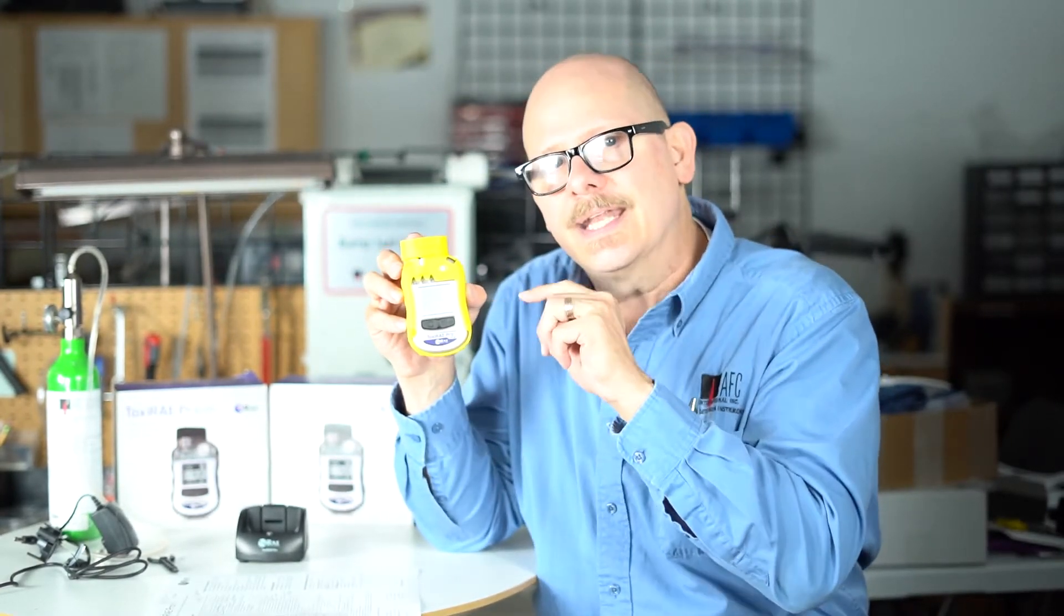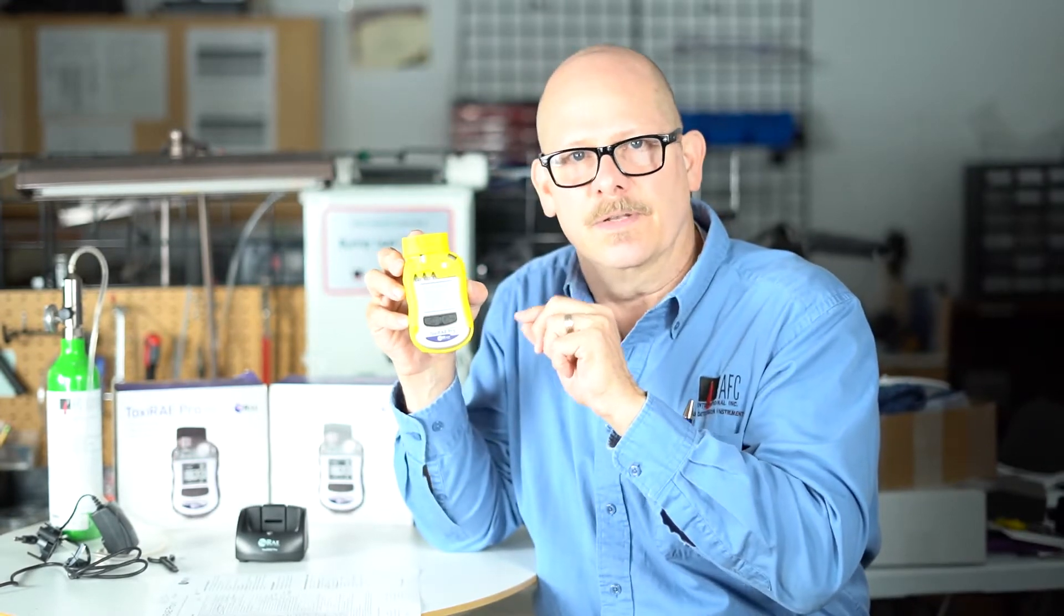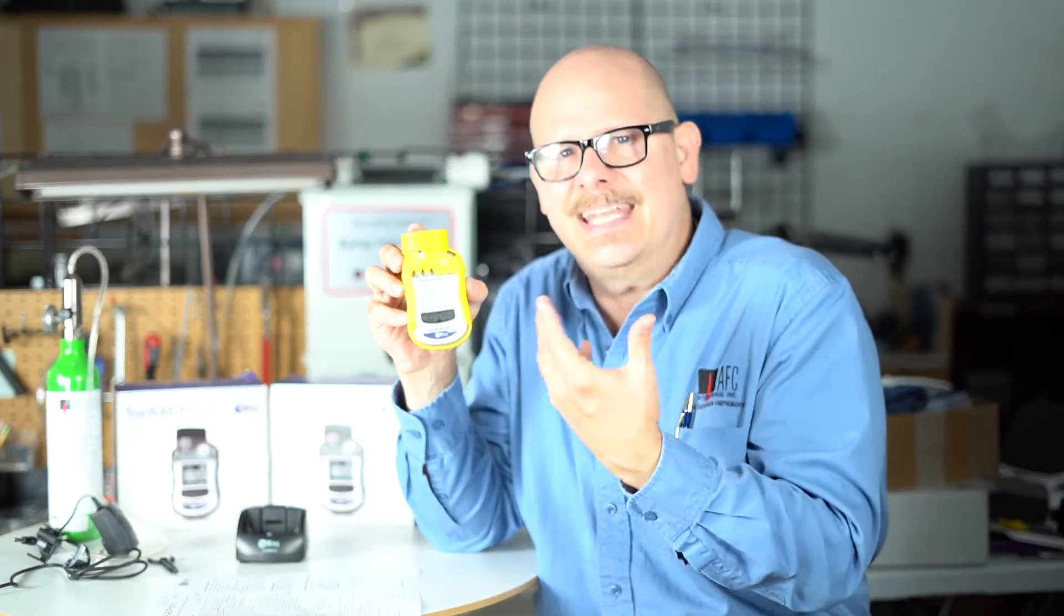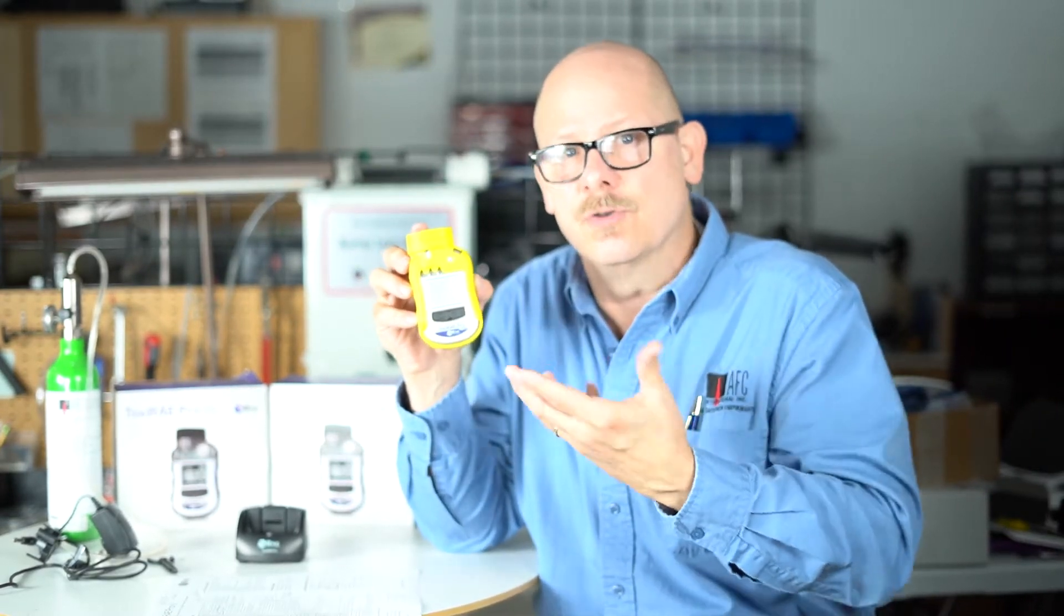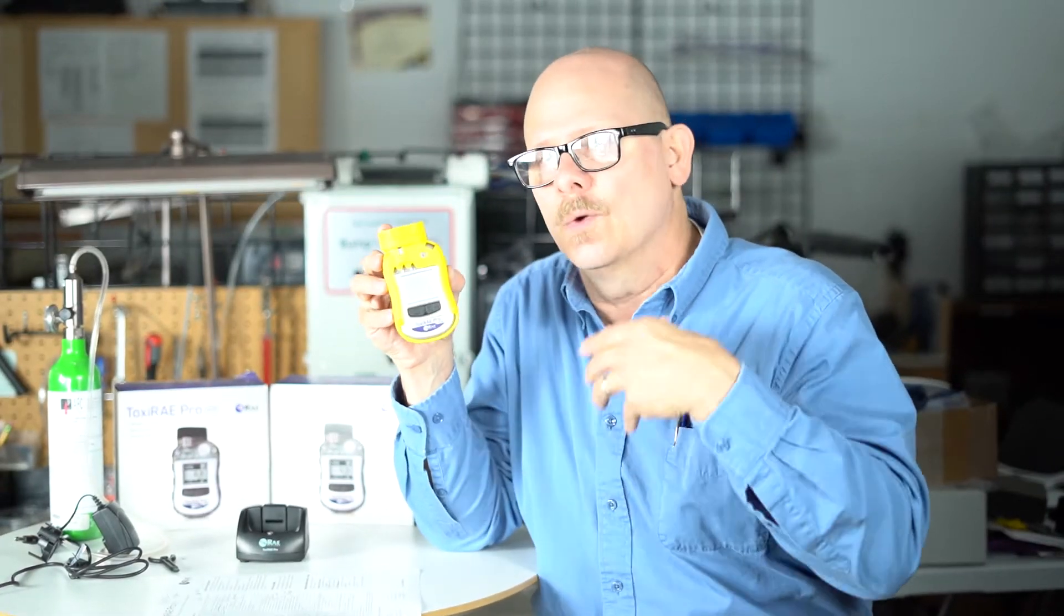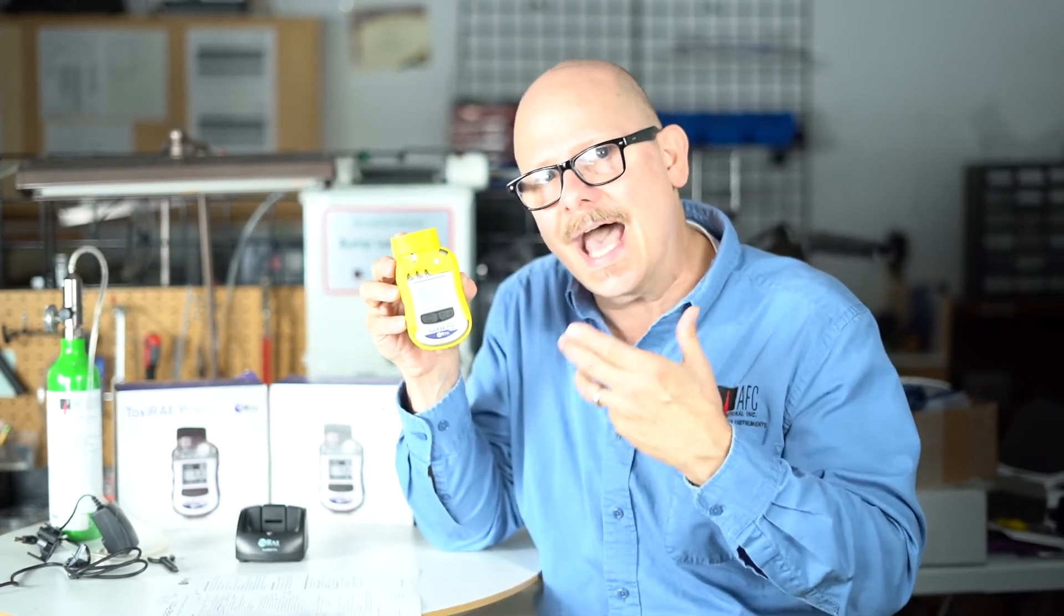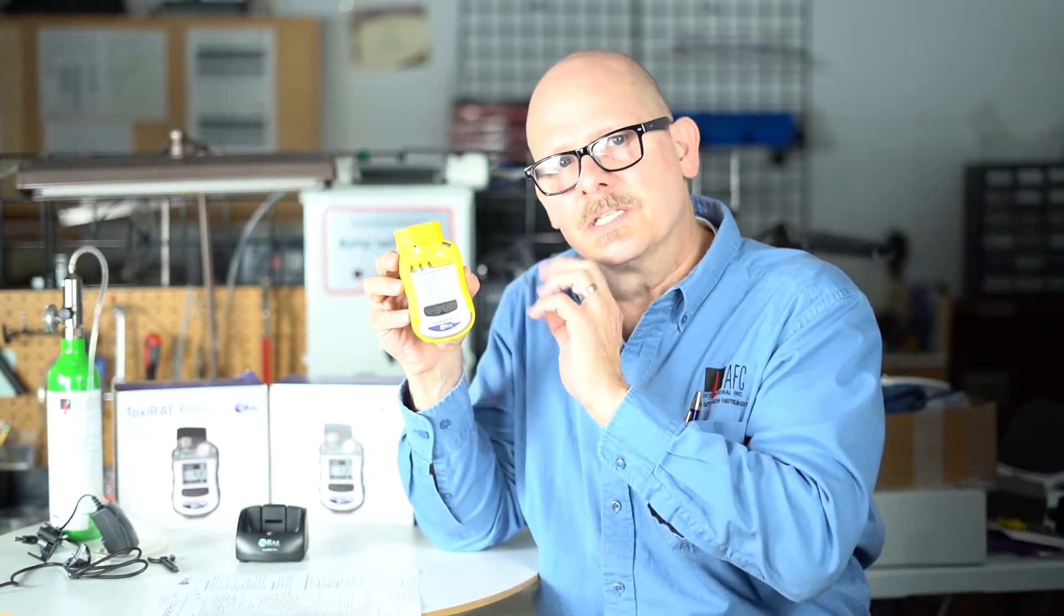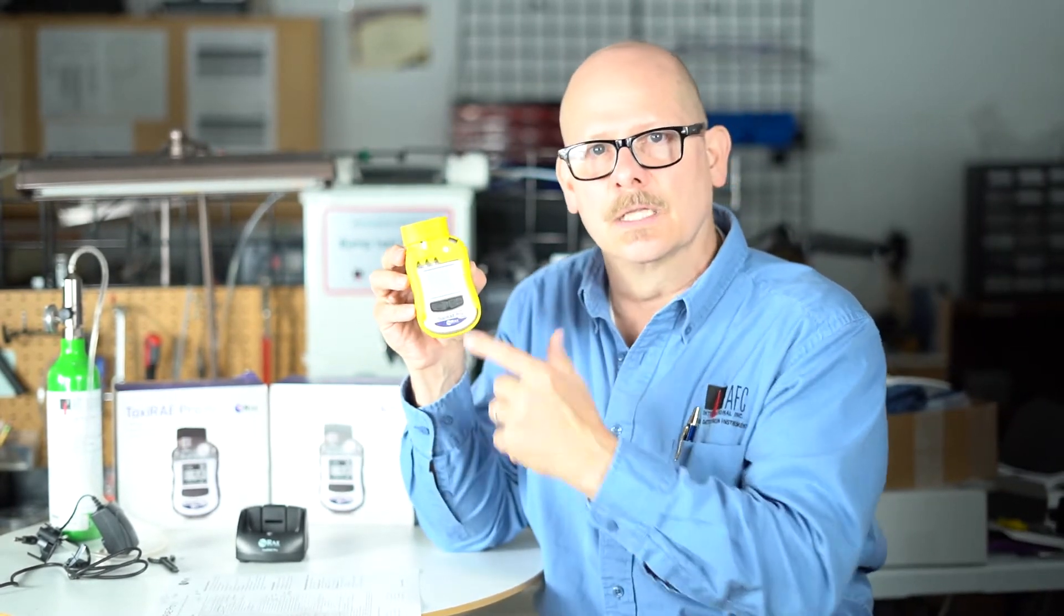In addition, it has a short-term exposure limit, 15-minute STEL alarm, so we can actually set that to go off if we've exceeded any kind of higher concentration STEL that you may come across. We want them to make sure if they're exceeding high concentrations, they can get out. So you'll get a special, separate STEL alarm, and the display will say STEL alarm on it.